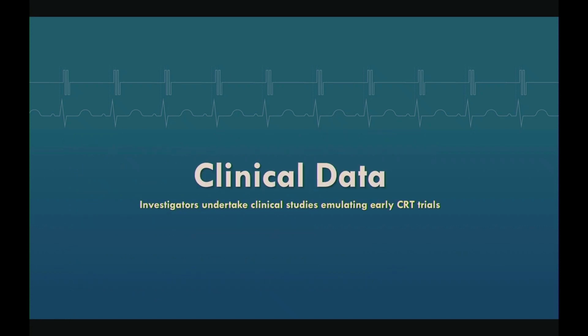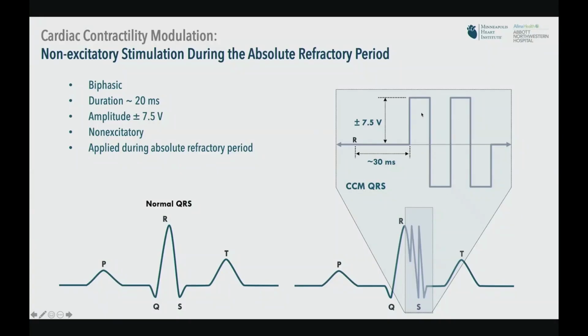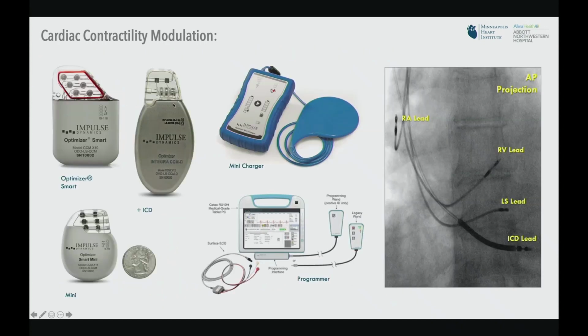So looking at the clinical data, the current device uses a double biphasic voltage signal that's seen here. This is the equipment that's currently out. This is the optimizer, which is the main device that's been studied. You can see there's 3 leads, an atrial lead and 2 ventricular leads. So there's a right ventricular lead that functions as the lead that provides the signal, and there's a local sense lead that assists with timing. And you can see these a CCM device in a patient with an existing ICD.